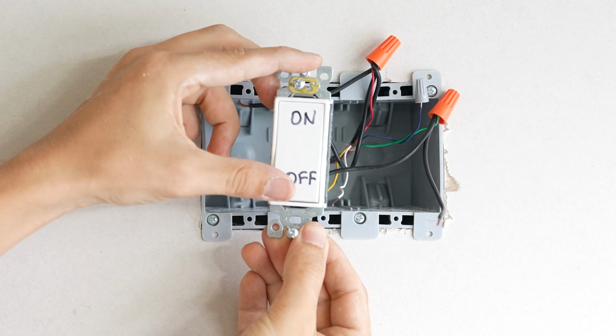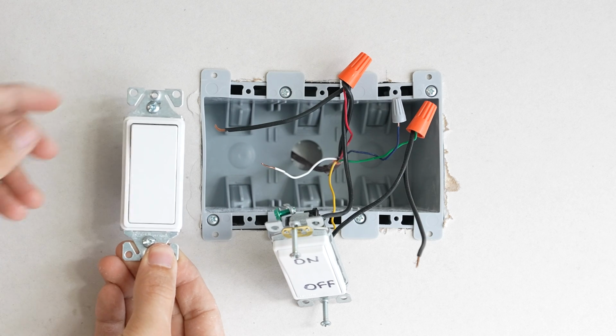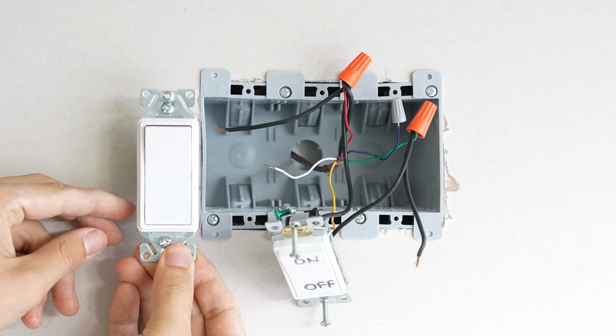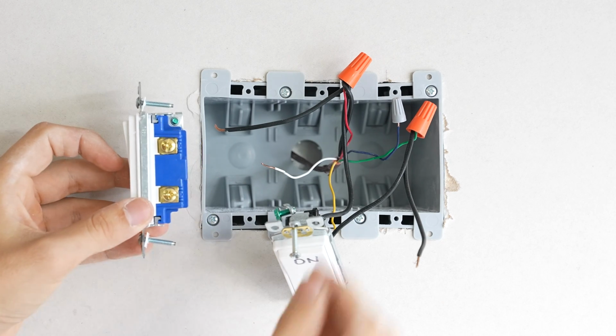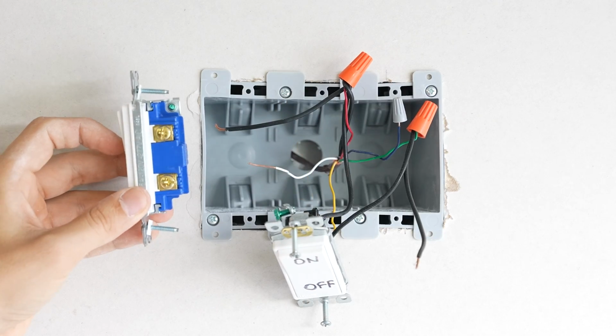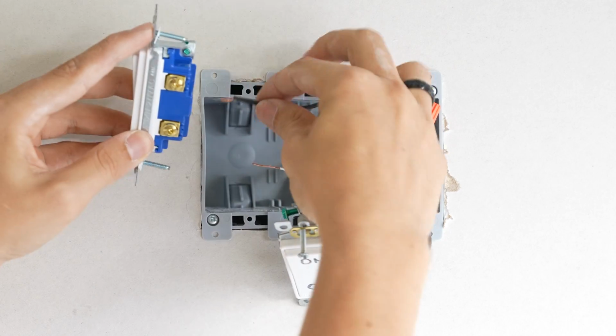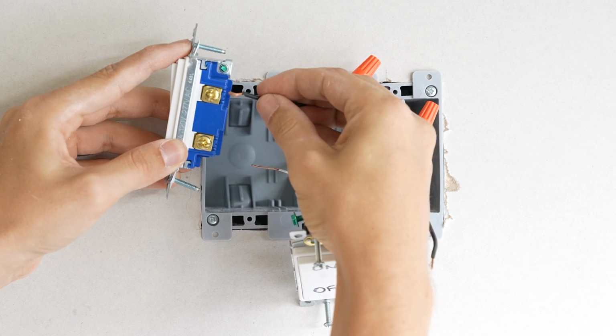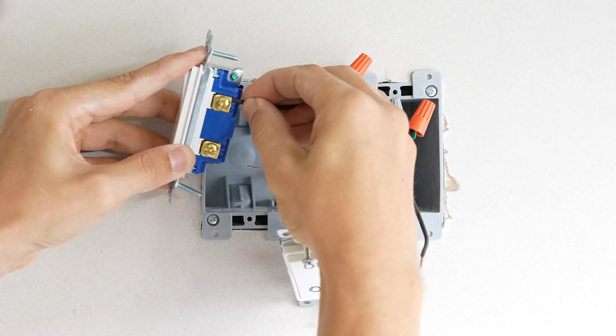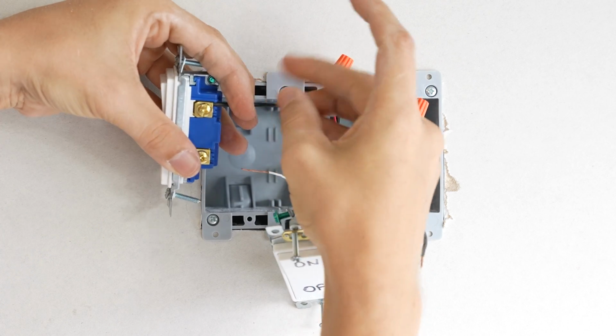turning them both on. Next up is the furnace switch, and just like the AC, a power wire goes into the top terminal, and the white heating wire goes into the bottom. With heating, there's no need for the indoor blower wire, since the furnace itself will automatically turn it on after it preheats.